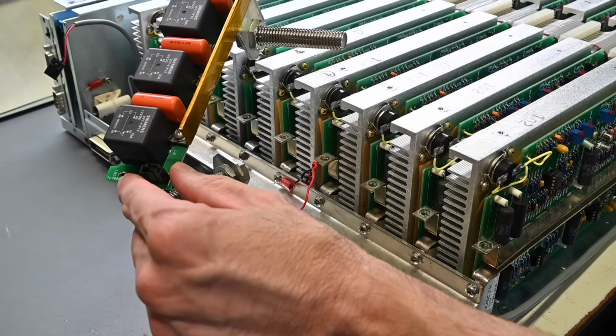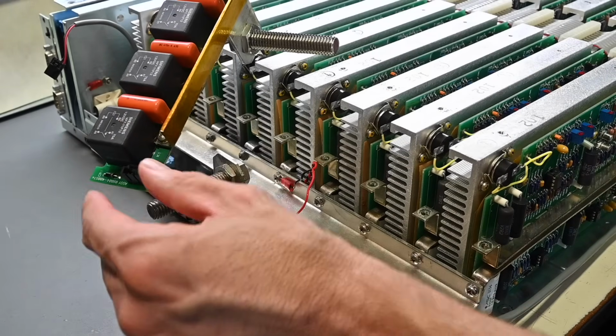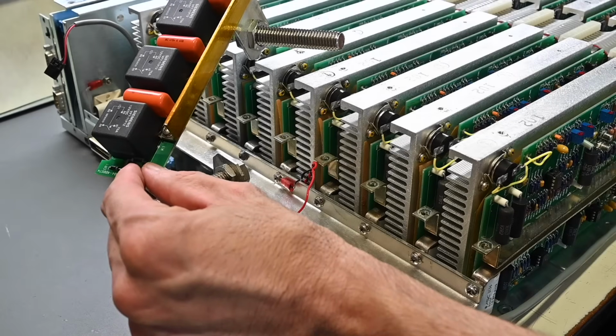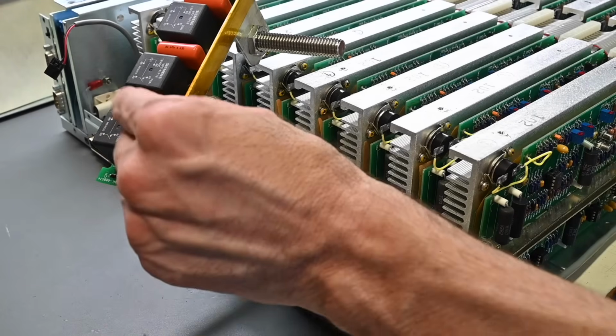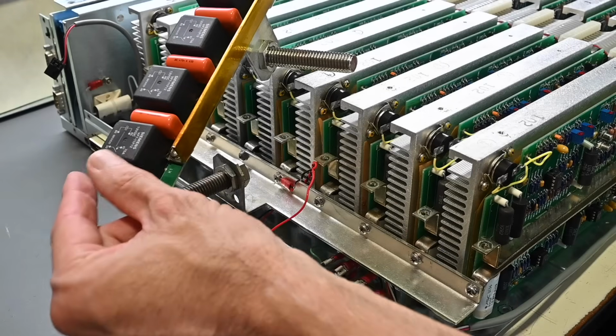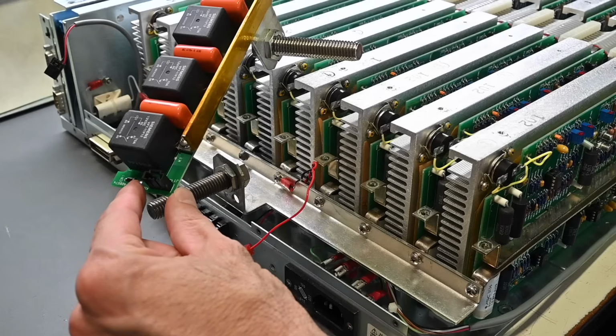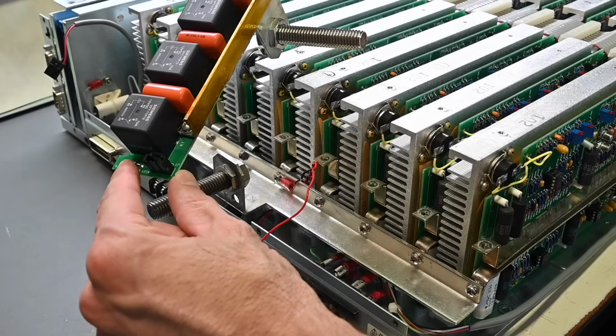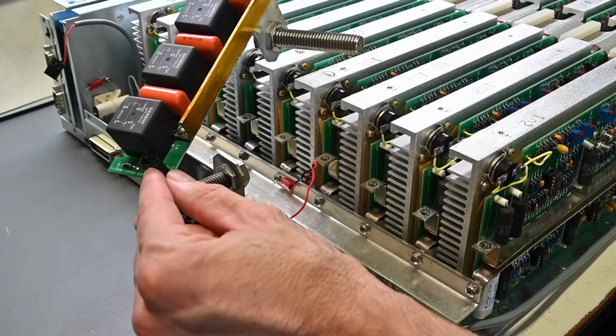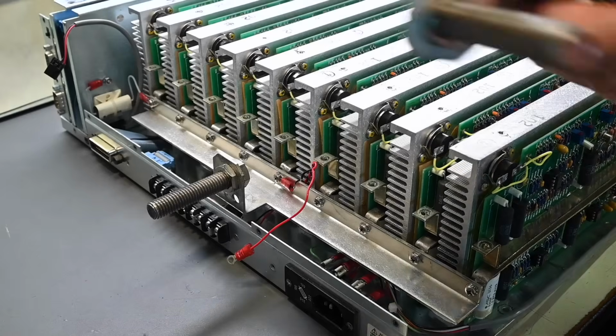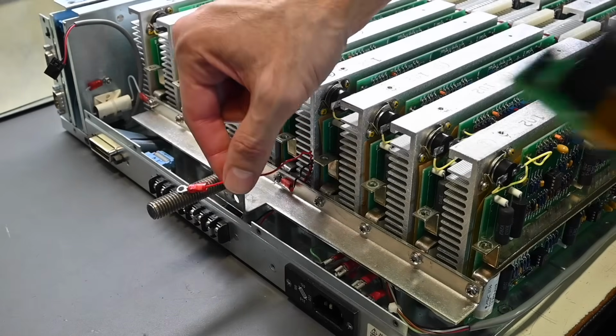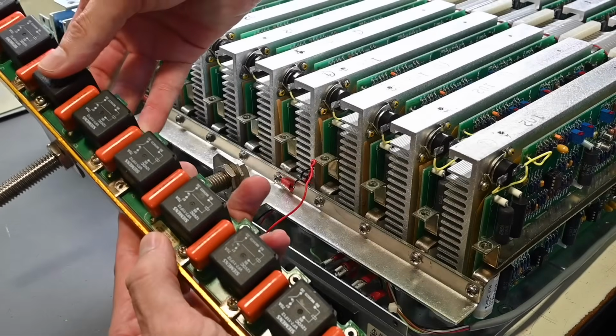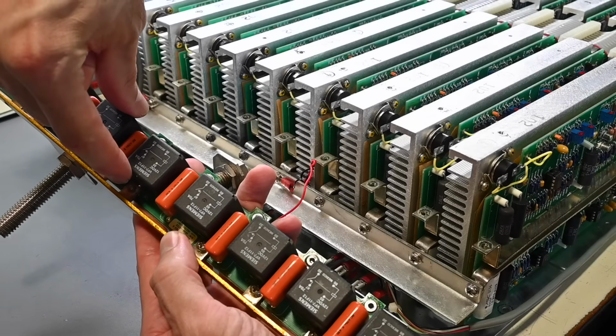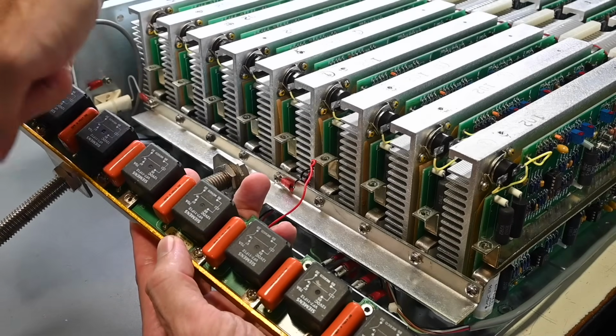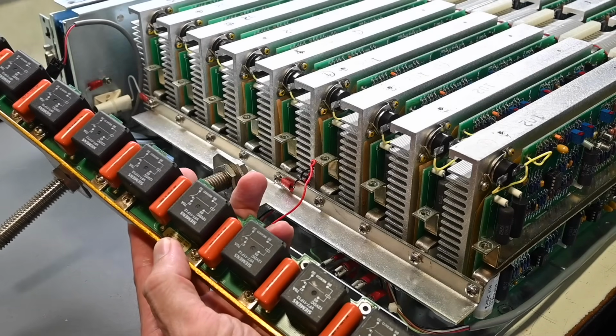So that diode normally is not conducting when the relays are turned on, but when the source voltage is removed, then this diode conducts that kickback voltage, because again, the kickback voltage is the opposite polarity of the applied voltage, and that's when this diode conducts. So the diode, again, is in reverse polarity from the applied voltage. And right here you can see this red wire that has to attach right down in here, the terminal. So that's the voltage sensing, and it's on the unswitched side of this assembly.